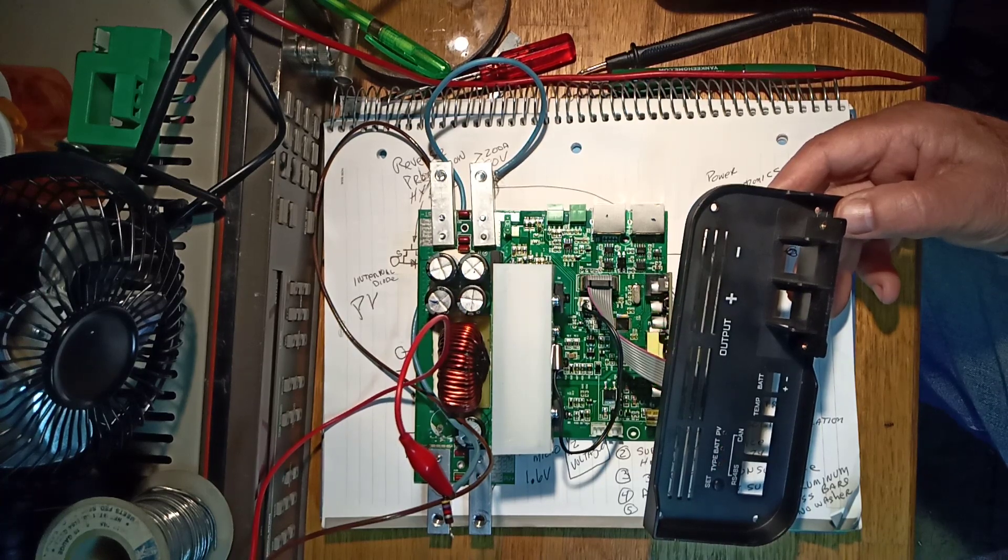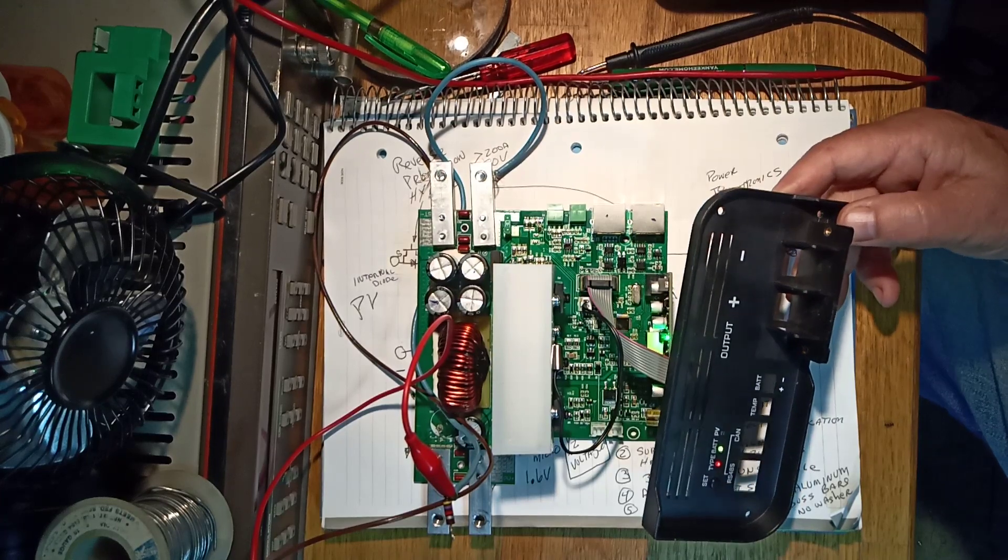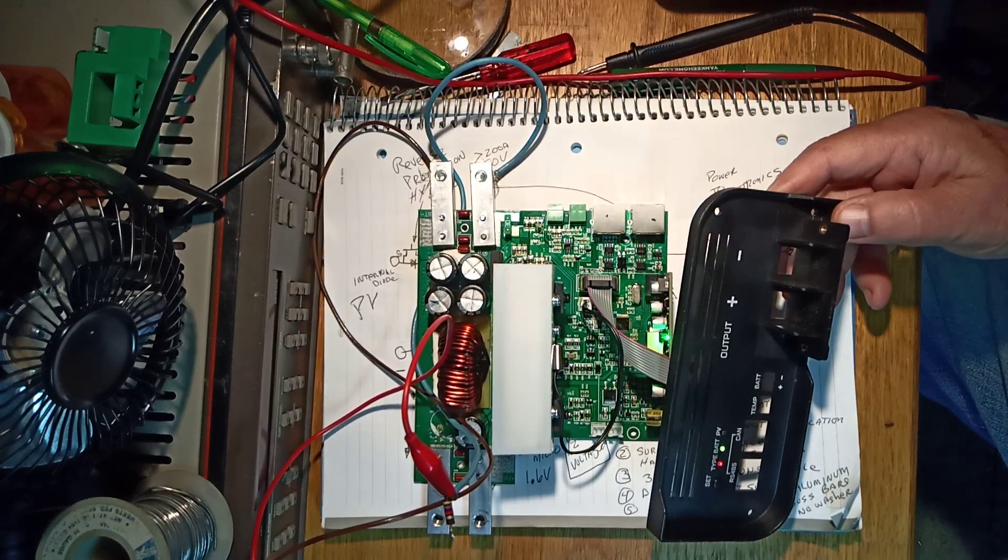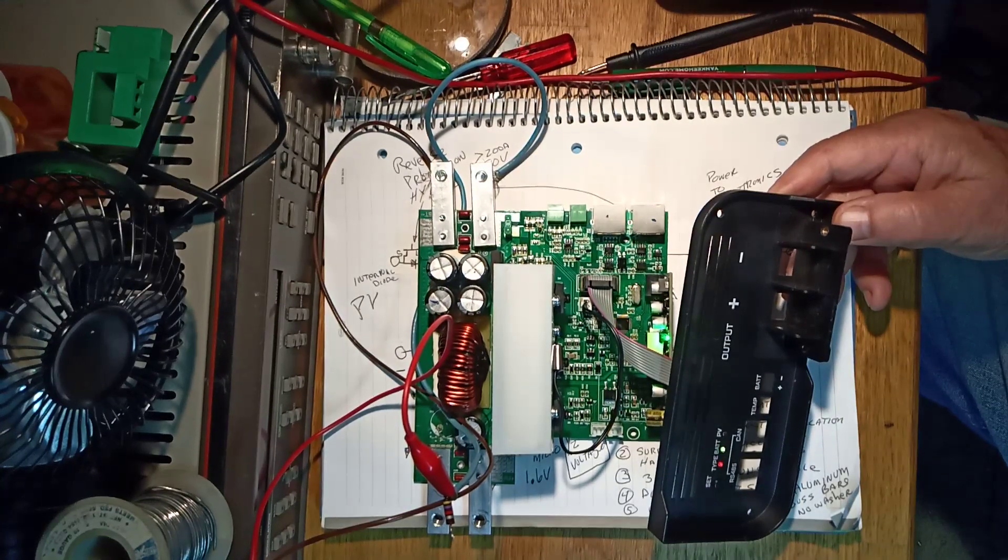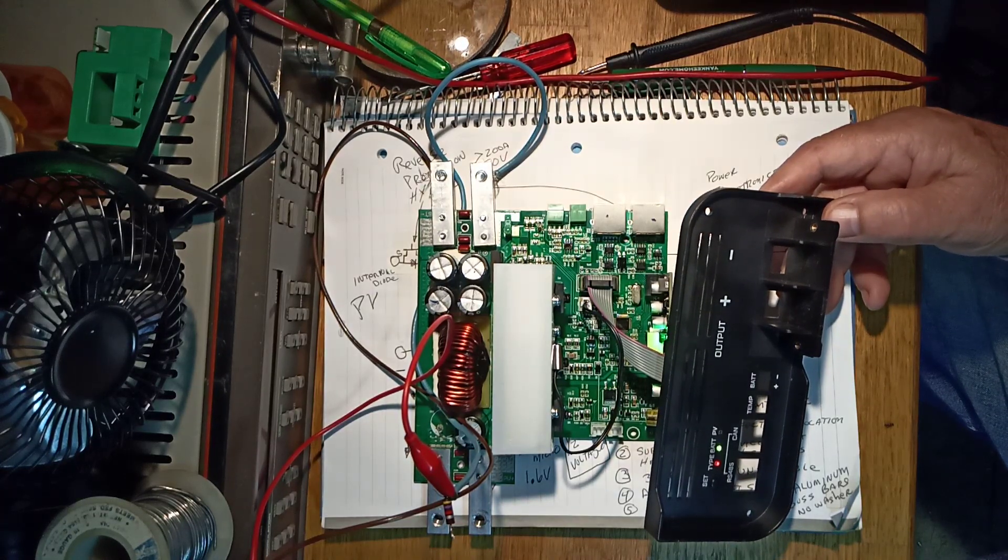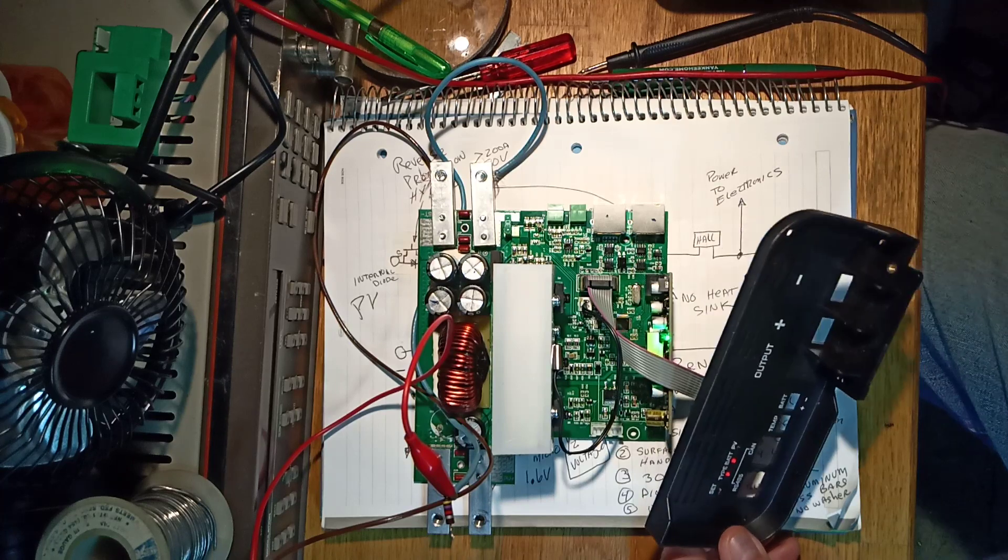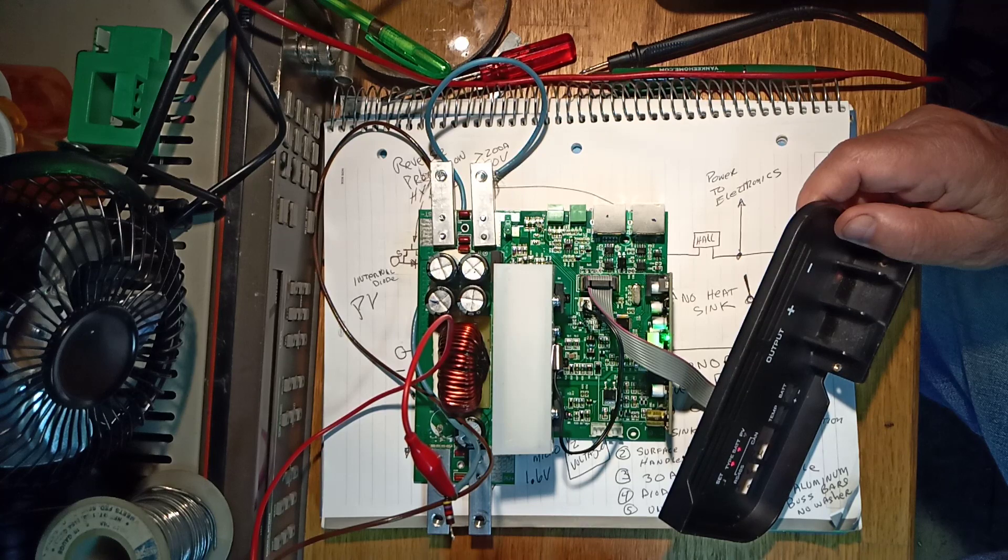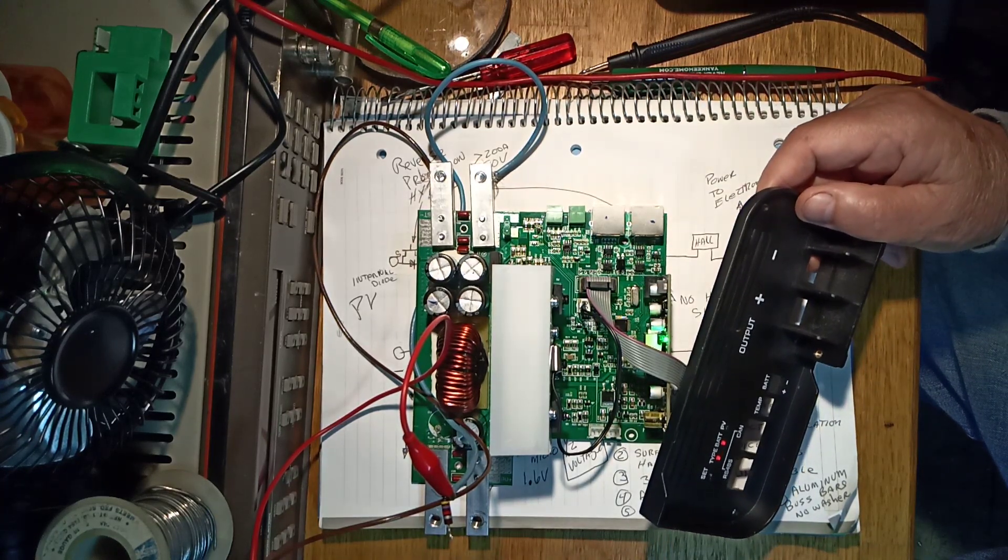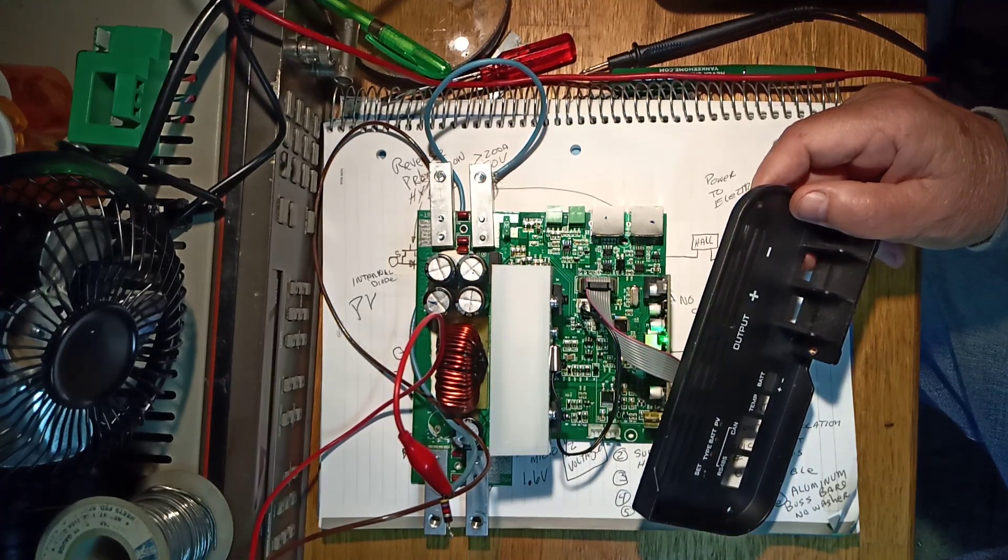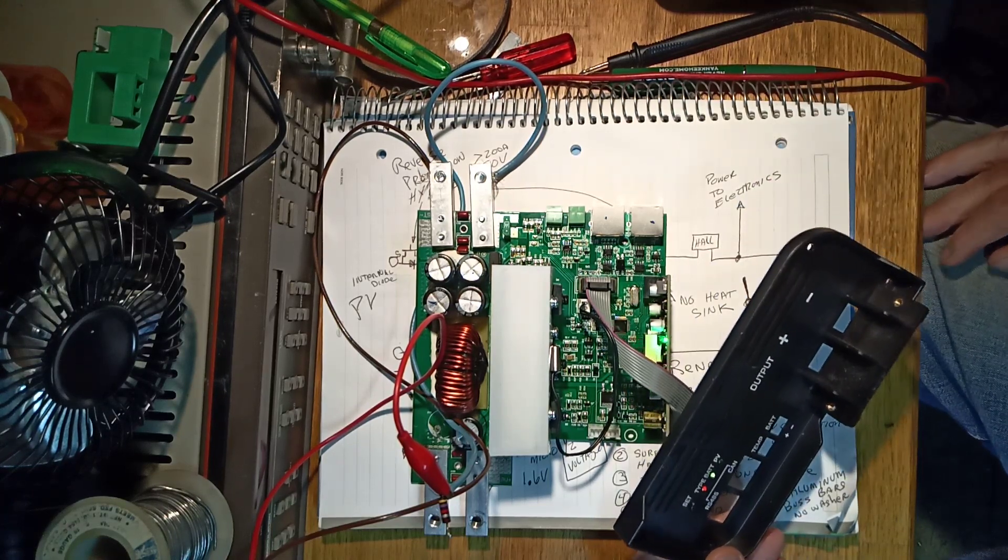If you bring up the voltage on the batteries, you have to disconnect the system because it just stays in a shut off position. About 34 volts will shut the thing off. If you remember that, you have to disconnect the batteries to reset the thing. It's at 37 volts. Remove the power, put it back on, and green light. Close the door and the light stays on.